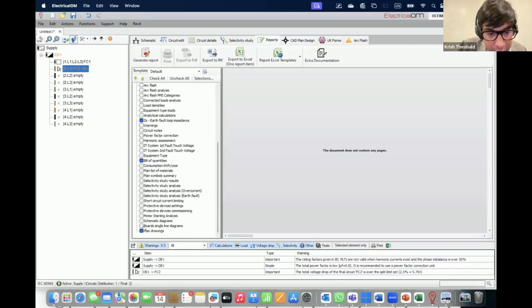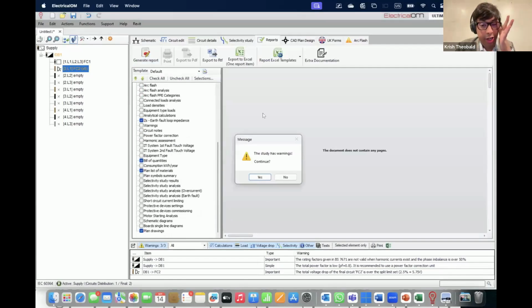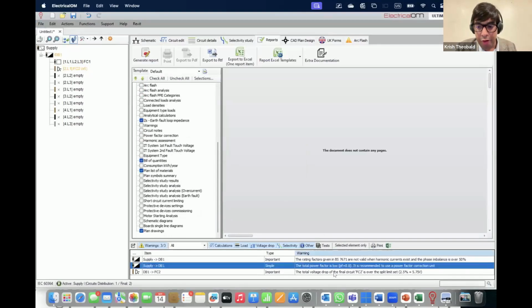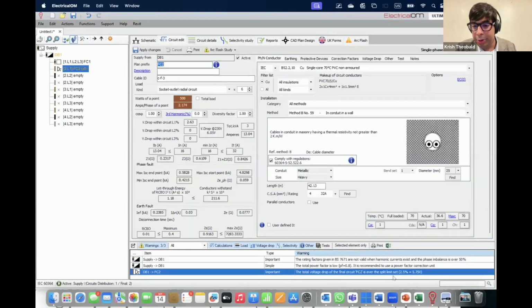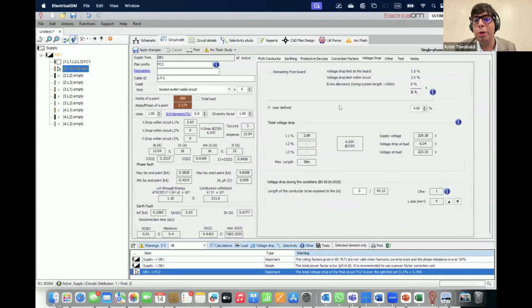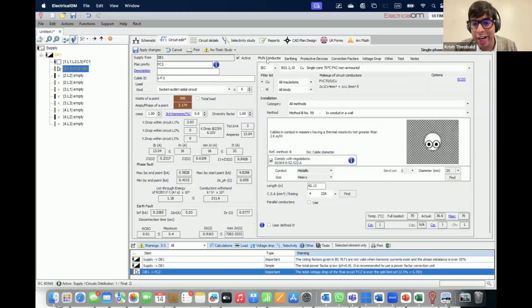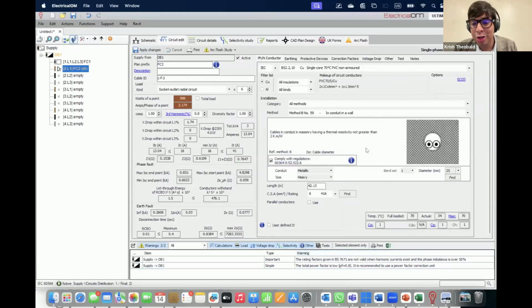plan drawings as well, plan list of materials. So if I generate a report, obviously it's now giving me warnings because let me show you what the warnings are first. So yeah, power factor obviously, and now it says that it is beyond the limit, which is fine because I have set it to 4% here. But if I go back to the limit, it's still 2.89. So then I'll need to do 6 square mm actually. So now that warning will go away.